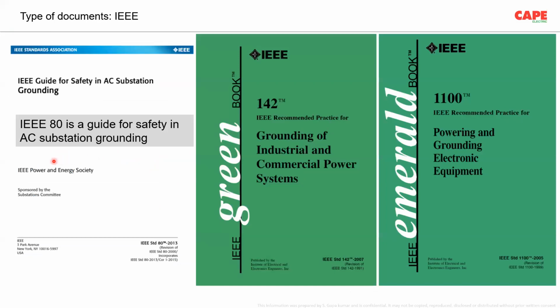So the standard which is always referred to in India for earthing and earth enhancing compound is the IEEE 80. Of course, it is one of the best guides available, which can be supportive to make an earth grid in soil in order to reduce the step and touch potential. No doubt about it. But the only point is, a lot of the time people are using these techniques for earthing in low voltage electrical installations, which is absolutely wrong.